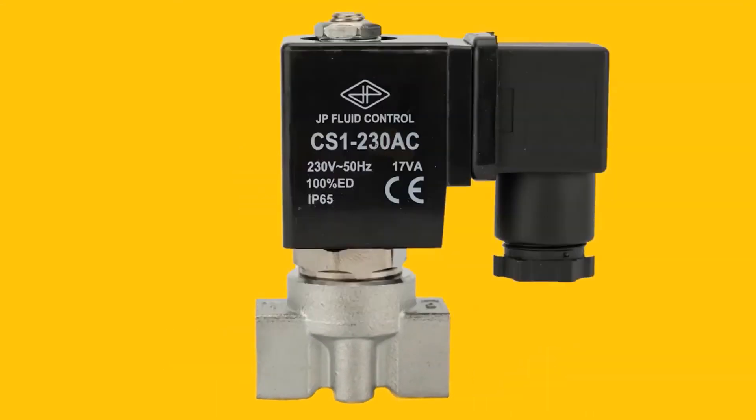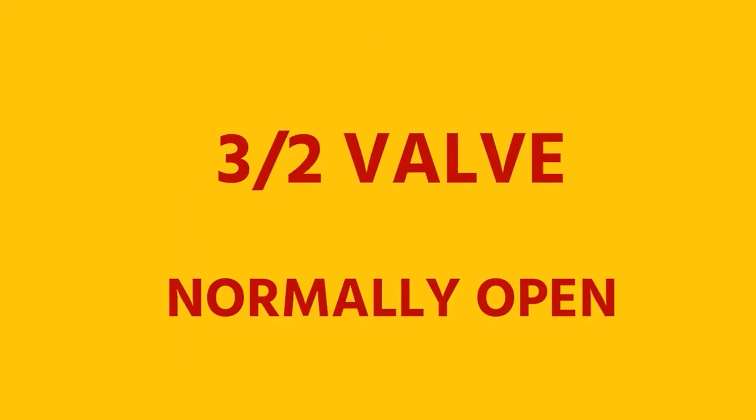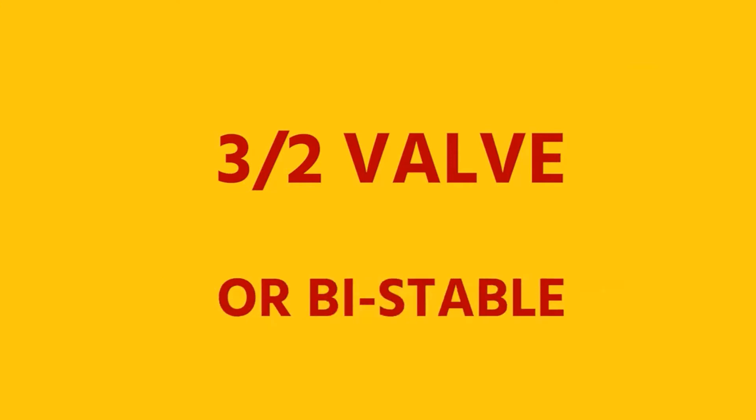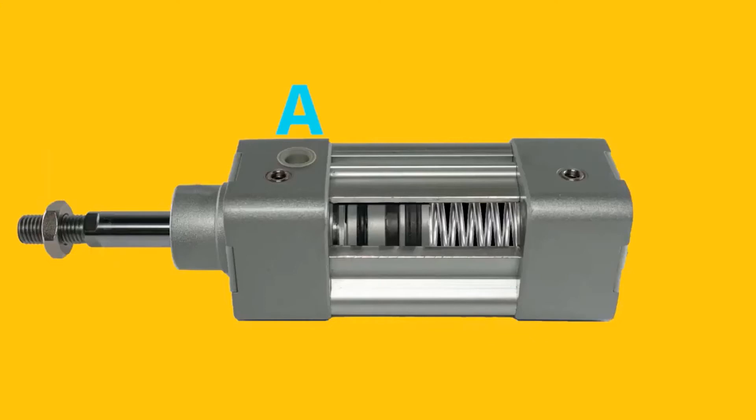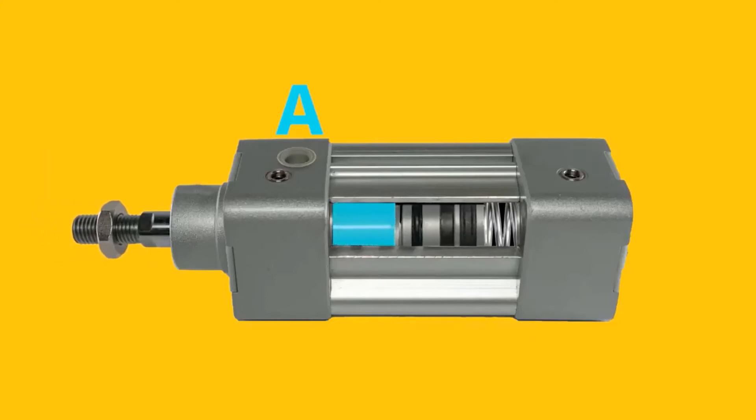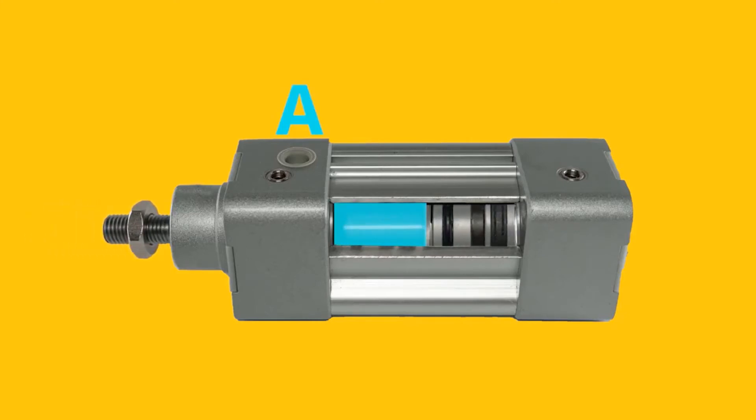A three, two-way valve has three ports and two states. These valves can be normally open, normally closed or bistable. They are used when your appliance needs to be either vented or pressurized. An example is a single acting cylinder. The valve fills the cylinder through one port but also vents the cylinder afterwards through the same port to realize a new working stroke.